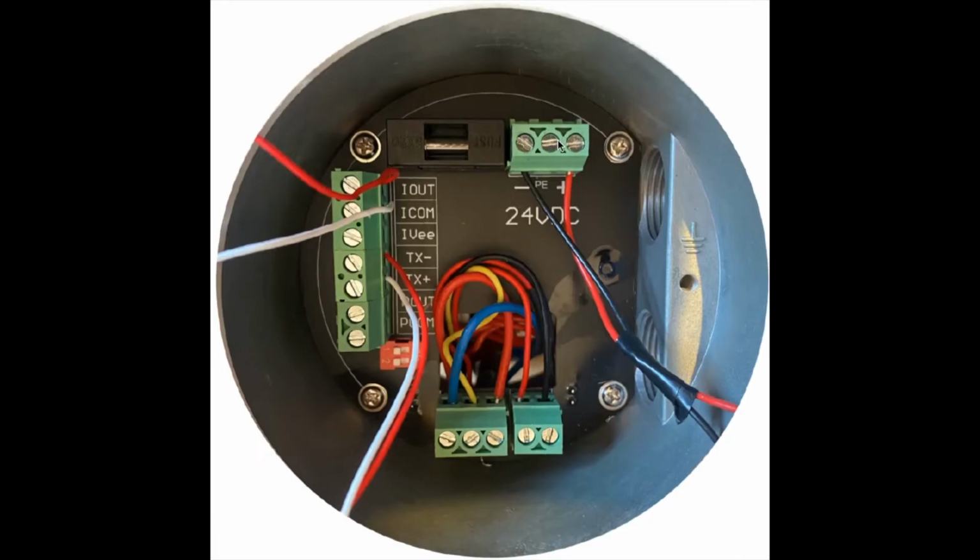We show the inside of the enclosure with the power, 24 volts DC, 0.5 amp max, plus on the right, next to the plus, minus on the left. Here's a place to put ground. These terminals are for the sensor and coils on the mag meter that make it a mag meter.